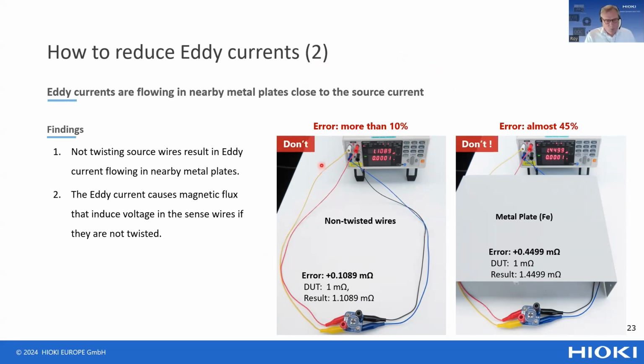But this gets a lot worse if we bring a metal plate near the test wires. You can see the accuracy of the measurement dropping, with a measurement error of 45%, related only to the effect of eddy current. So you can see that the impact of eddy current can be very, very high.